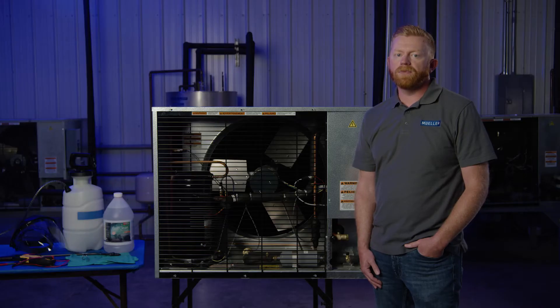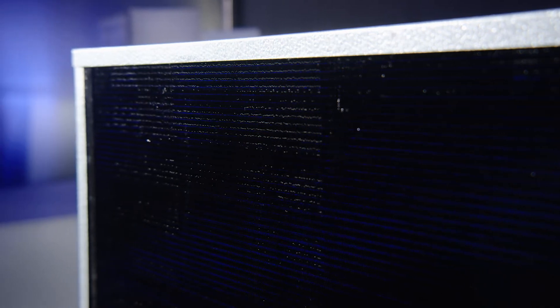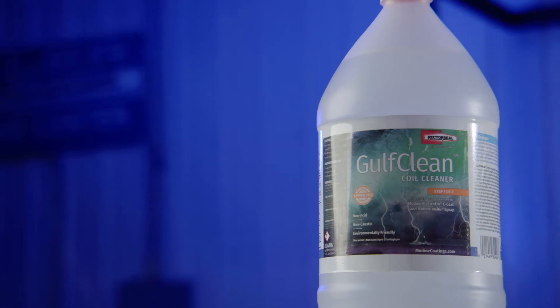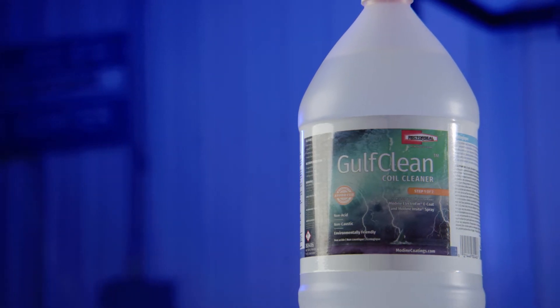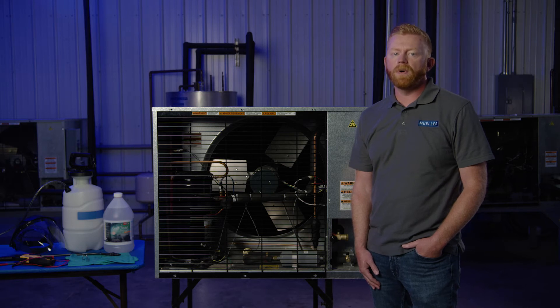For this demonstration, we are using a Mueller E-Star Hyperform condensing unit. Notice the dark coating on this condenser. Mueller began using a corrosive resistant coating on all E-Star condensing units in October of 2020. For Mueller coated condenser coils, use only GulfClean Coil Cleaner to keep coils intact and working properly. Other cleaners can strip the protective coating from the coils.